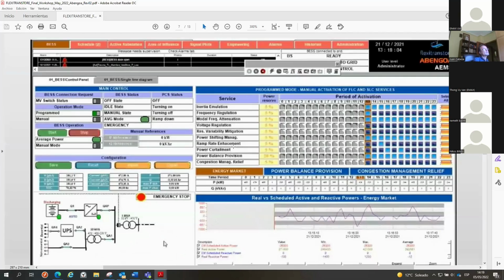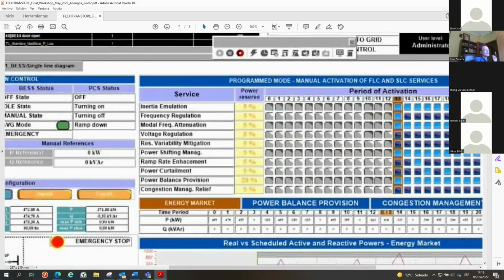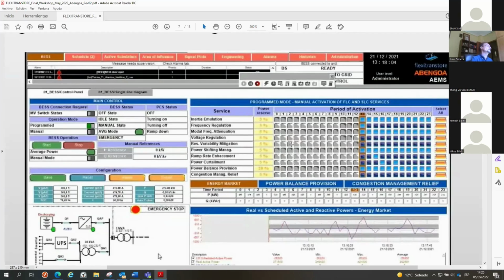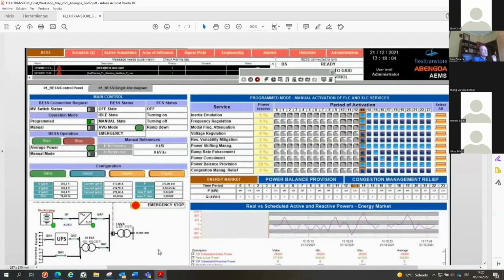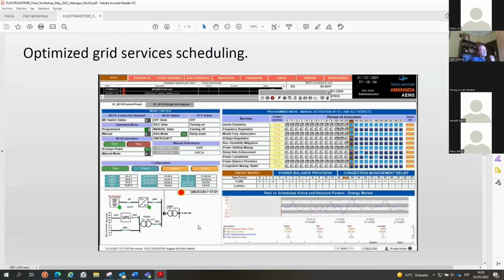Here you have the grid services that the BESS can provide. With this template, the TSO can select the hours in which each service needs to be activated and the amount of power required to mobilize for each service. This is an input to the third level controller, which determines the best optimized power dispatching that can be used. If this power dispatching is acceptable to the TSO, the schedule is loaded into the control system of the BESS, so that it is automatically performed the following day.